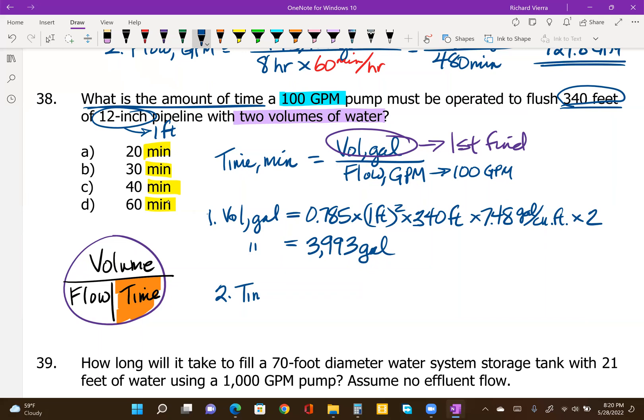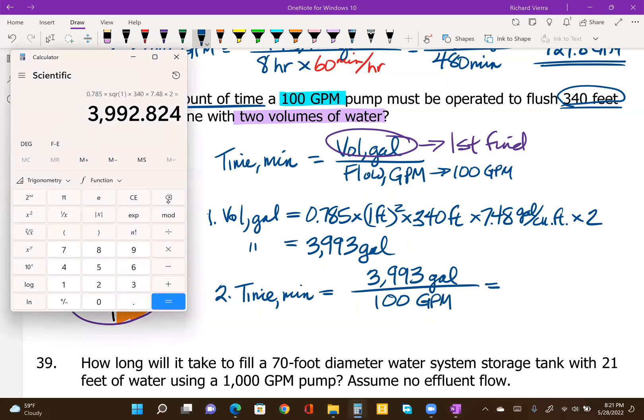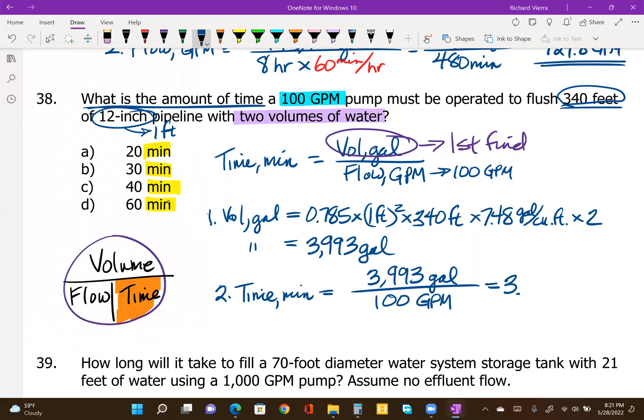So now we have that number as well as the flow rate of 100 gallons per minute. So we can set up the time calculation in minutes. So we do the volume, 3,993 gallons, divided by the flow of 100 gallons per minute. So divide that 3,993 number by 100, and we end up with 39.9 minutes. So we'll go with answer C. Run the pump for 40 minutes, and that should flush it through twice.